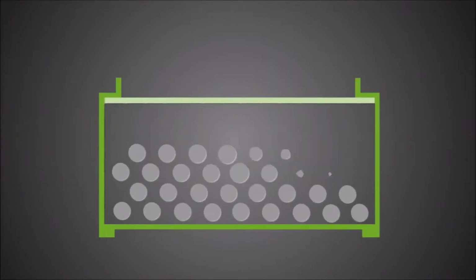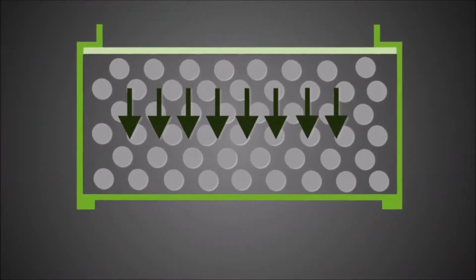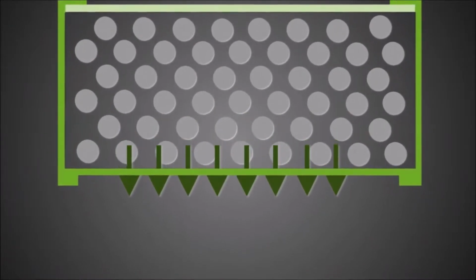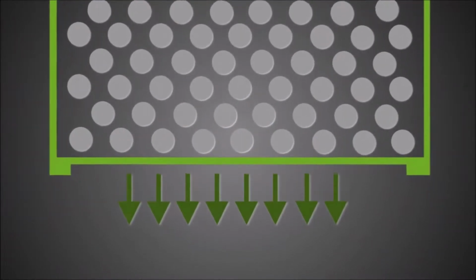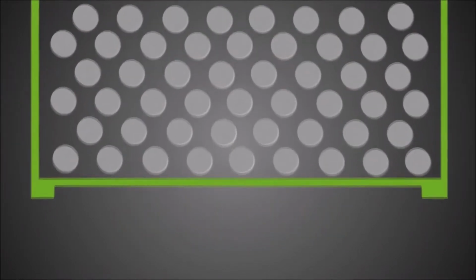BOFA have selected a range of carbons to cater for all known gases of the industries they sell into. Activated-based carbon for organic solvents generated during PCB assembly processes. Acid-washed carbons for ketone from applications within the printing sector. Phosphoric impregnated carbon to remove formaldehyde found within fumes generated by laser markings of plastics.